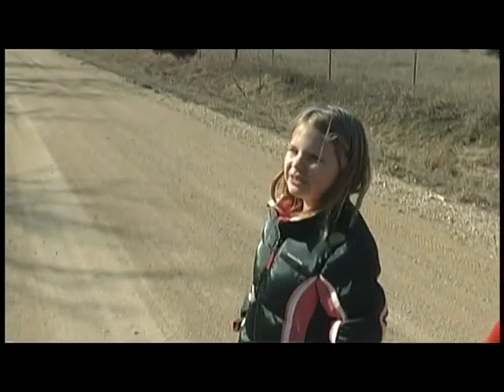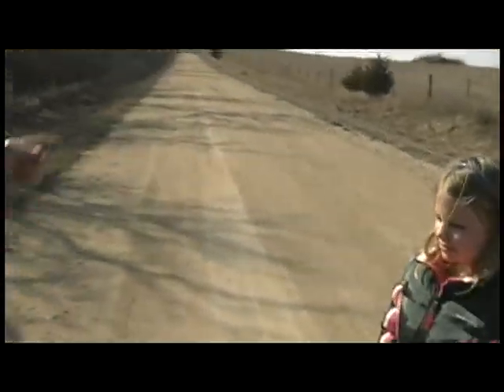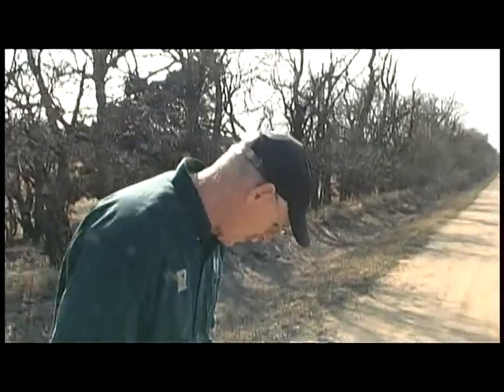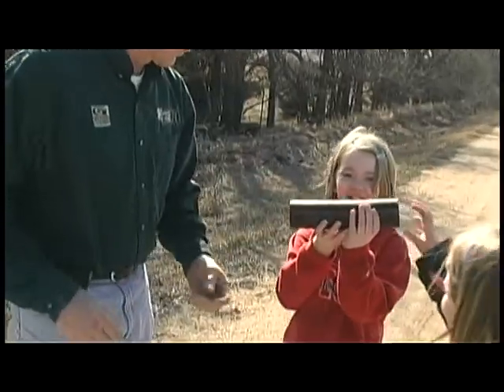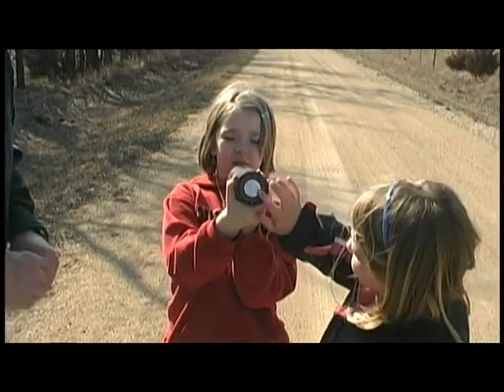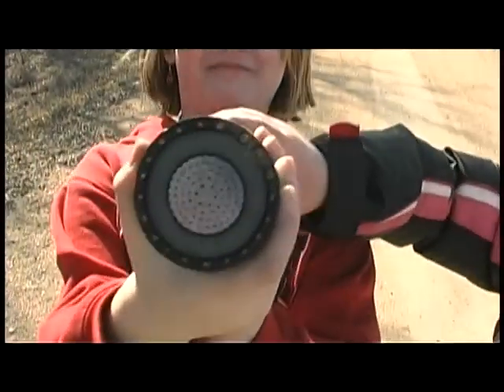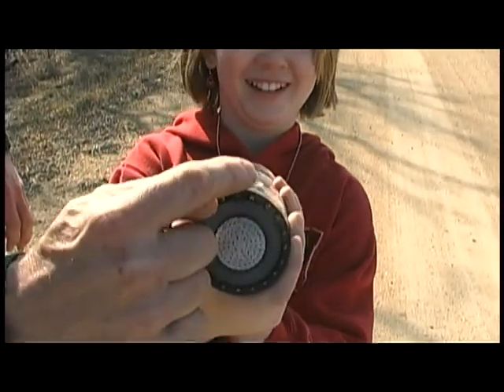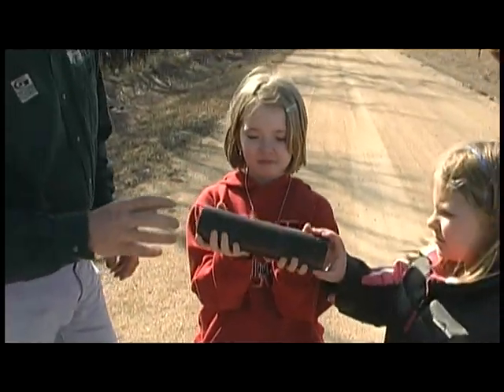How do you get the energy to different cities and towns? That's a good question. The electricity off of those actually comes down and it goes underground, and there's wires underground, and this is one of the wires actually that goes underground. It goes into what they call an underground collection system, and this part right in here is the conductor of the electricity, and then out here on the outside you see little pieces of copper. That's a shield on the outside of that, and that's a ground.